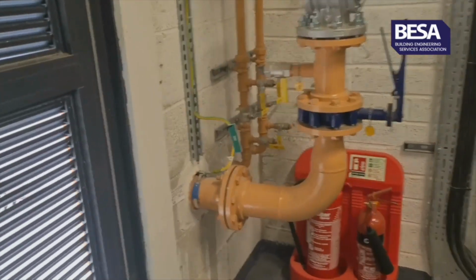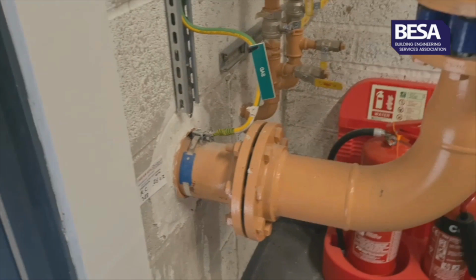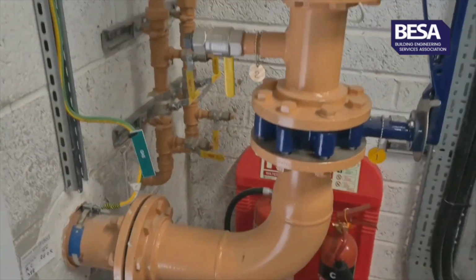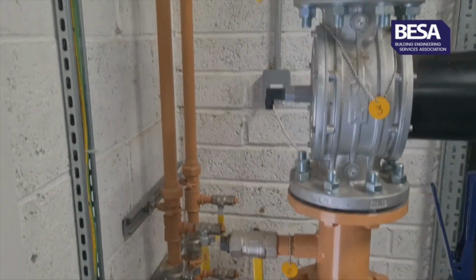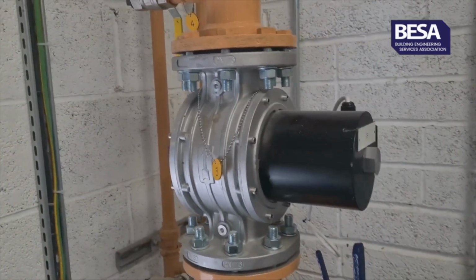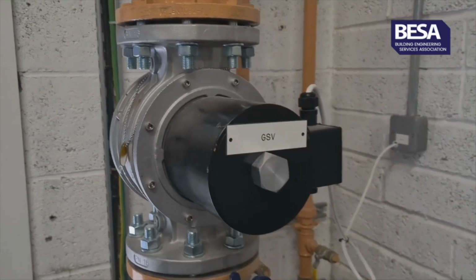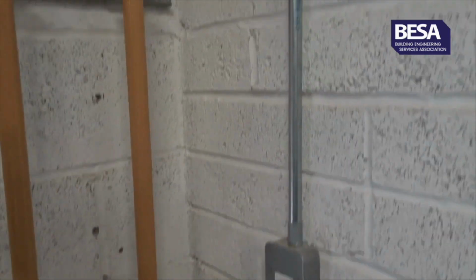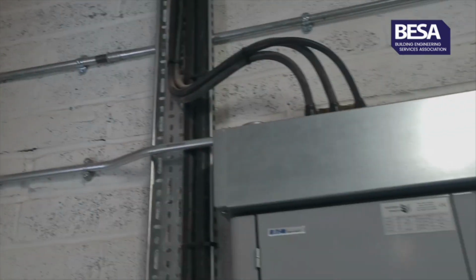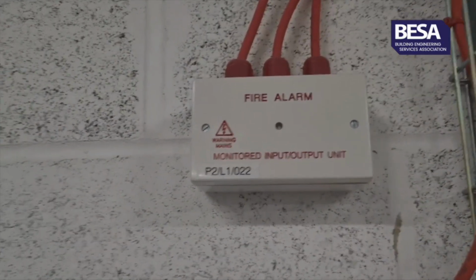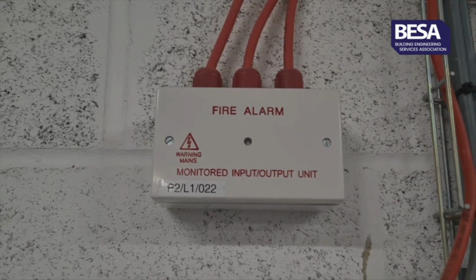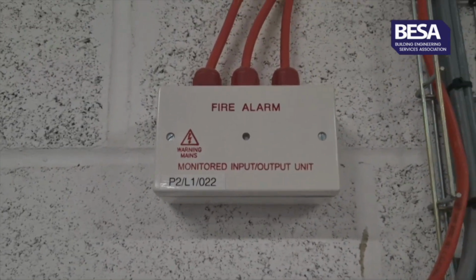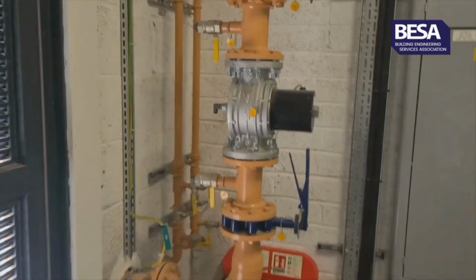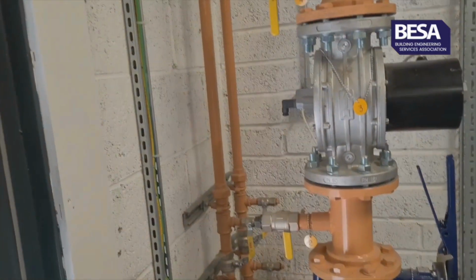Coming around here to the incoming gas, so incoming gas through the wall, comes from a kiosk over at the boundary. Isolation valve, test and purge points, gas solenoid valve there, which is wired back in and goes into the trunking and then comes back to the panel. There's a fire alarm interface module above the BMS panel that's wired into the panel. On activation of the fire alarm, the gas solenoid valve will shut. Again, that's all been tested and signed off.